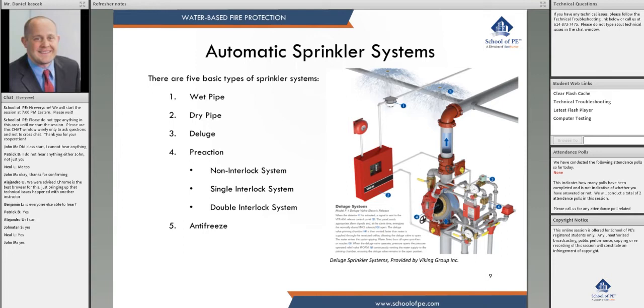A pre-action system is meant to do one of two things. A single interlock and a double interlock are meant to reduce accidental releases. A non-interlock is used when we have a very large dry area, such as a warehouse that can't be maintained at temperature, and a dry pipe system would be too large — over 750 gallons.